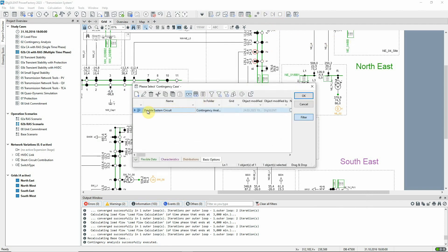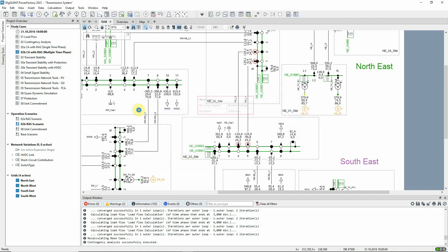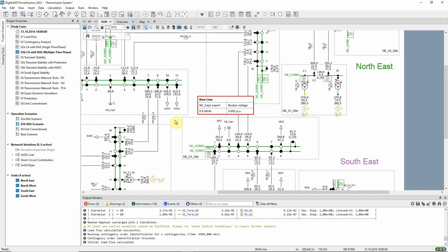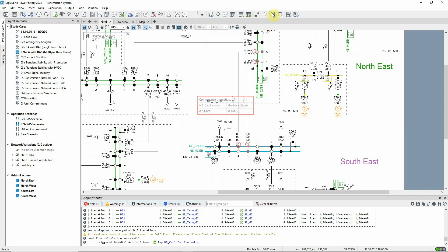The first step is a base case load flow. The next step is a time phase 1 at 1 minute. The fault case is executed and the voltages drop. This triggers the RAS and so starts the timer for the events.